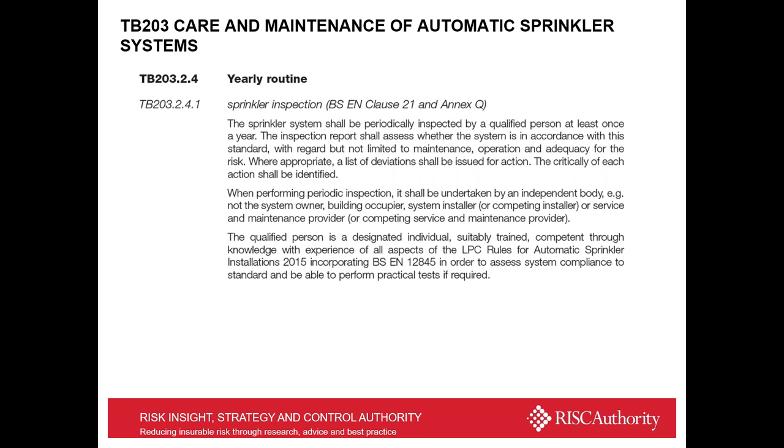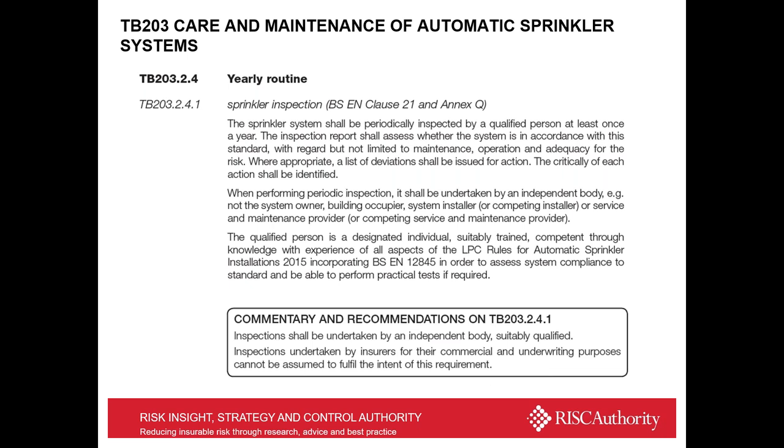It's a designated individual, suitably trained, competent through knowledge with experience of all aspects of LPC sprinkler rules, and also able to perform practical tests if required. It cannot be, as stated in the second period there, a competing installer or competing service and maintenance provider. So LPC sprinkler systems should be independently inspected, not by sprinkler contractors. And again, undertaken by an independent, suitably qualified body. In the commentary and recommendation, inspections undertaken by insurers for their commercial and underwriting purposes cannot be assumed to fulfil the intent of this requirement.